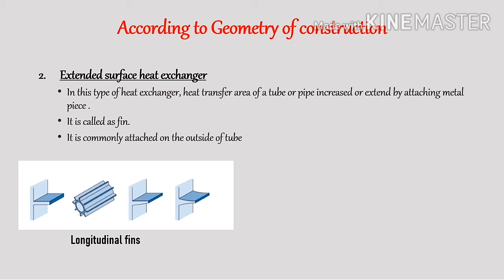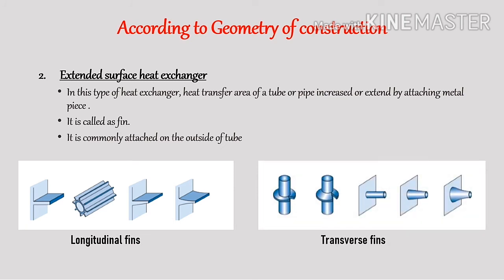The second type of fin is the transverse fin, where long metal pieces are attached to the outside of the pipe at right angles to the axis of the tube. It is used when the direction of flow is across or at right angles to the tube. This type of fin is used for cooling or heating of large quantities of gases.